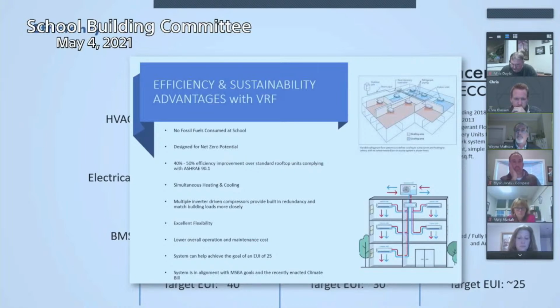So when you're trying to get to these extra goals, these are the things you have to look at. This fourth point is really key in school construction: simultaneous heating and cooling. As a school, you don't have to decide whether the whole building is in cooling mode or heating mode. With the Energy Conservation Code, we're not really supposed to do simultaneous heating and cooling, but with VRF you can, because the system takes heat from areas that want to be cooled and puts it in areas that want to be heated.